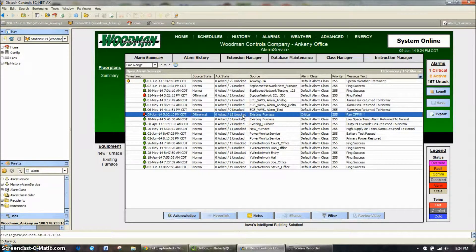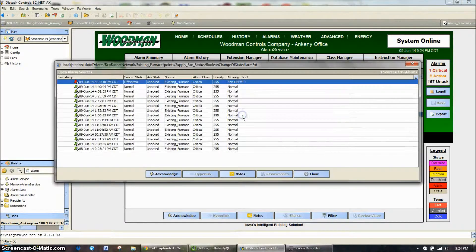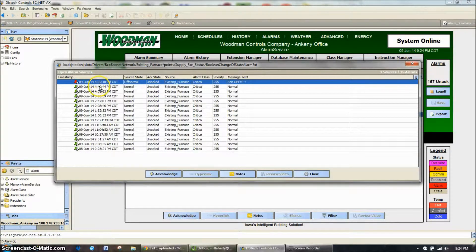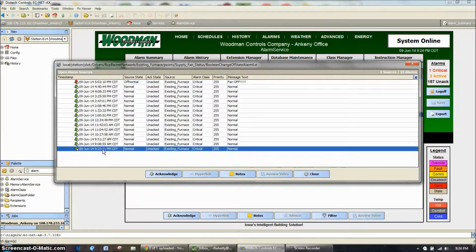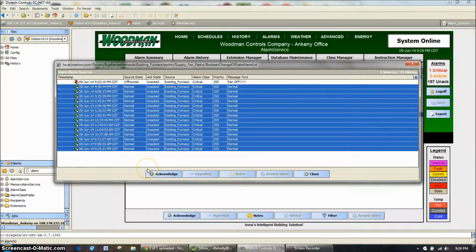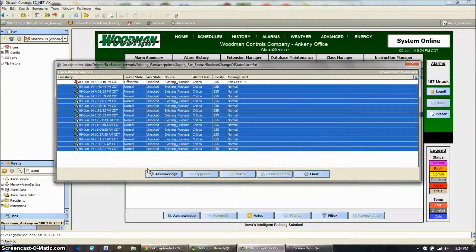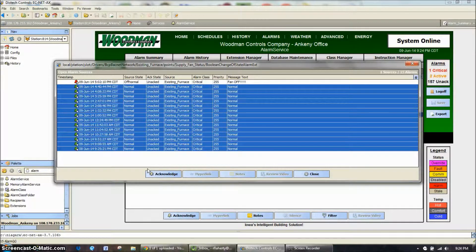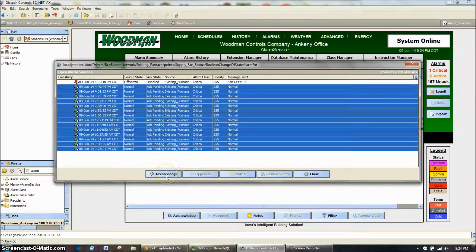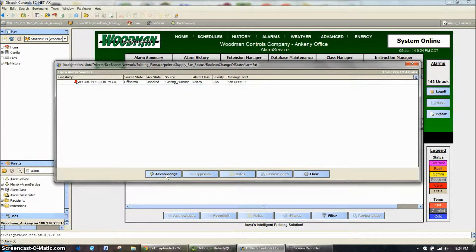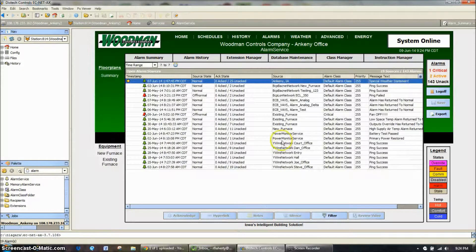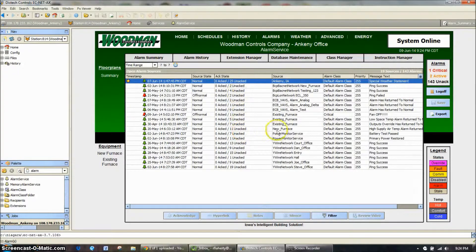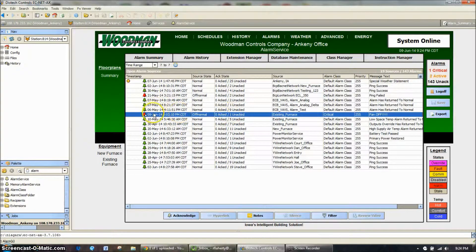So let's look at one right here, existing furnace, critical alarm, there's been 15 unacknowledged alarms. So clicking on that, we can go in and see, these are all the alarms that have happened, taken place, and they're not happening anymore. So since I know all those already took place, I know what happened, I created an alarm that is going into alarm every time the fan turns on and off at night. I can acknowledge these, and you'll see the acknowledge pending, and they will drop out of this database completely. And all you're going to see in here for this fan alarm is there's one unacknowledged alarm, and that's the one that is active.